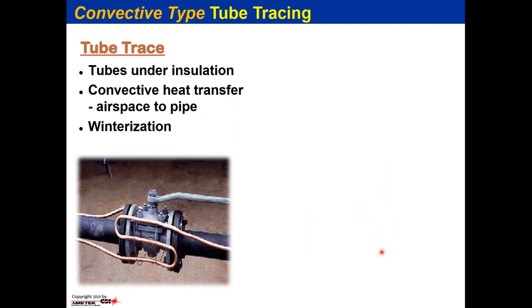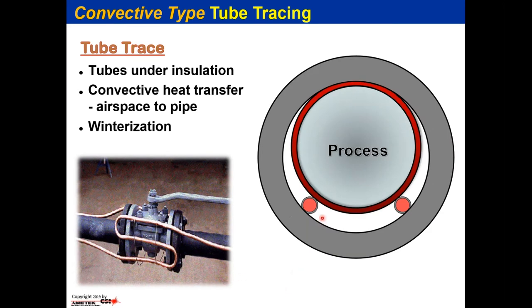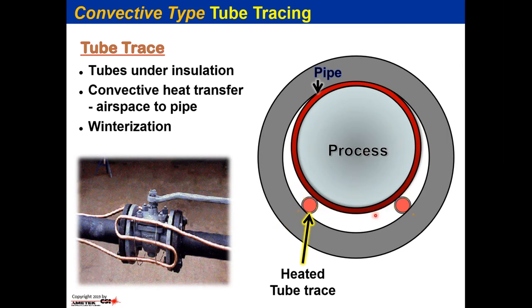The simple convective tube tracer — stainless or copper — runs down the pipe and around valves. In cross section, there's a very small contact surface where the tube touches the pipe, and heat convects through the air space to keep the process from freezing. We have the product pipe, the heated tube tracer convecting heat, and insulation surrounding everything to keep that heat from radiating outward.